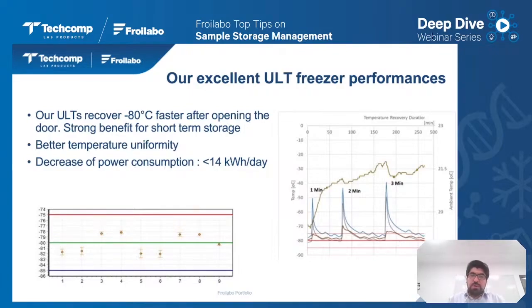Also, with the improvements we have done in the freezer, you can see our options. The temperature uniformity has increased. That means previously we had about ±5 degrees, as you can see on the bottom temperature, the red line and the blue line, which is the target of ±5 degrees. But our freezer's temperature distribution was closer to -80, and this also keeps samples safer in terms of storage and keeps the customer happy. Then I hand this back over to Olivier for the case study review.